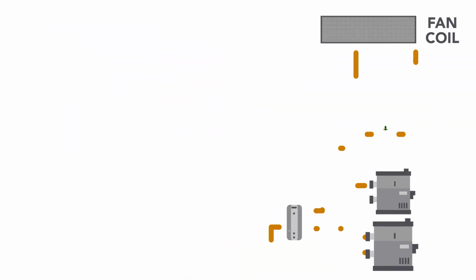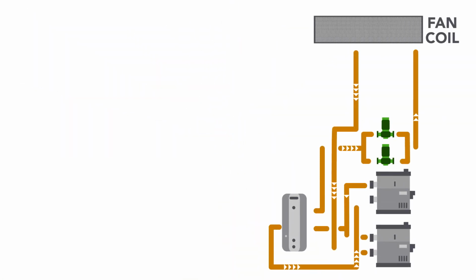When the space-mounted thermostat calls for heat, a 2-way valve opens and 140-degree domestic water flows through the coil and provides heating for the space. 140 is code mandated for storing domestic water to eliminate Legionella, so this temp is used as a design suggestion. However, if the max distributed water temp allowable in a building is 120, we would simply size the terminal unit to accommodate this lower water temperature. Once the water passes through the coil and heats the space, it is returned back into the return pipe at a 20-degree delta T or greater to be reheated.